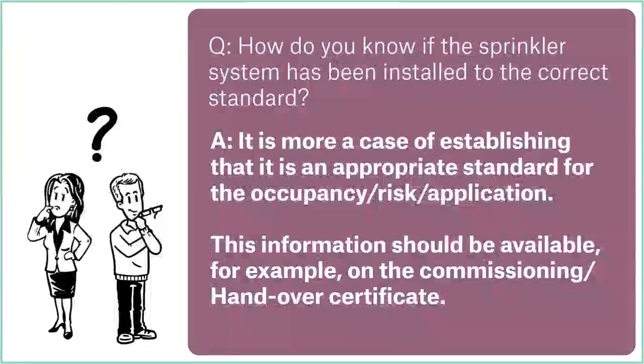I think we've talked about this in the past, where there is no requirement to bring the system up to the latest specifications. For example, if your sprinkler system was from the 1980s, then it would have been installed to a different code standard. Trying to think what it was now. Was it 5306? Yeah, 5306, I think, was the previous British standard for sprinkler systems. So obviously now we have 12845. So there's no requirement to bring that up to 12845 standards.